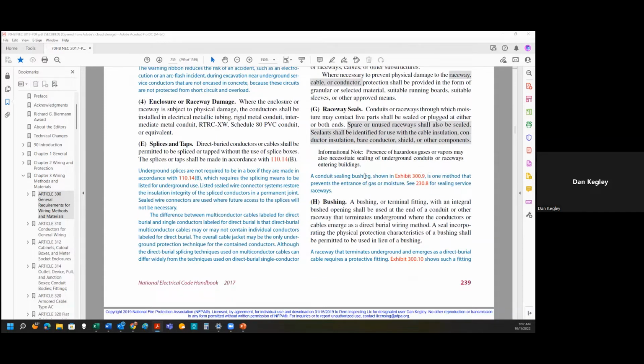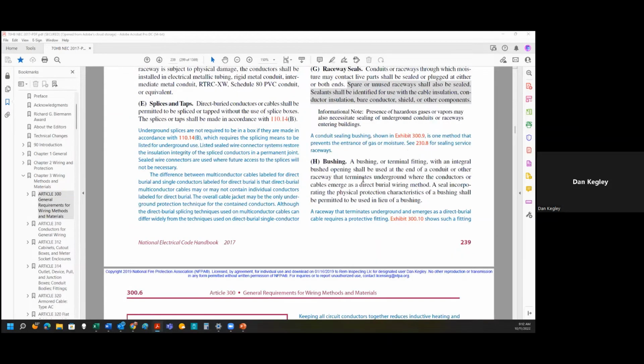Bushings on the end of the conduit, so on top and bottom of the conduit. So even though you have a straight piece of conduit that's cut off and stuck in the ground, it still asks for a nice rounded end bushing to be put on there, because as the ground moves, and believe it or not, the ground does move, it actually pulls on those cables and cords and connectors, and it will actually wear on the end of the edge of the pipe. So I want you to use a bushing on the end of it.